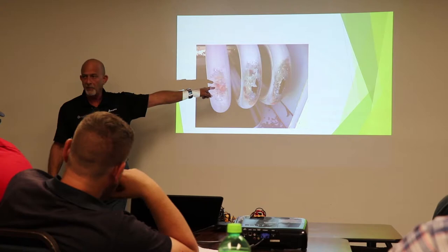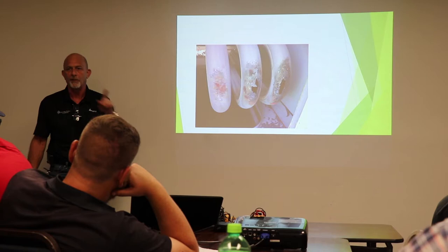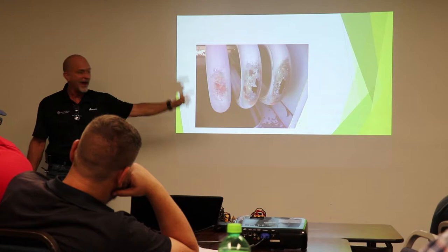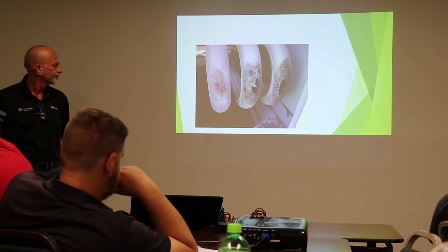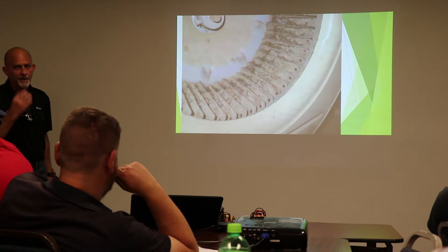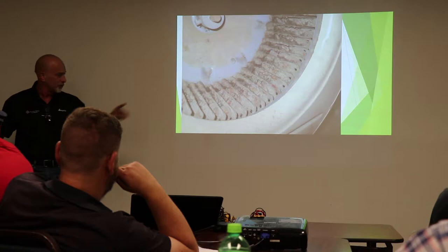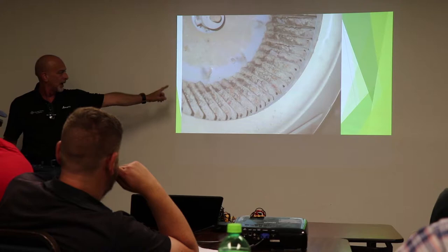Heat exchangers are designed to last a long time. Normal operation. That and that is not normal operation. That's misuse. Pull our blower housing out, looks like that, right? Now, as service technicians, if you're out there on a cheap cleaning check, you charge extra for that? You should. That should be an extra. I've had them just as bad where you had to physically take it to the car wash. You could not clean it.